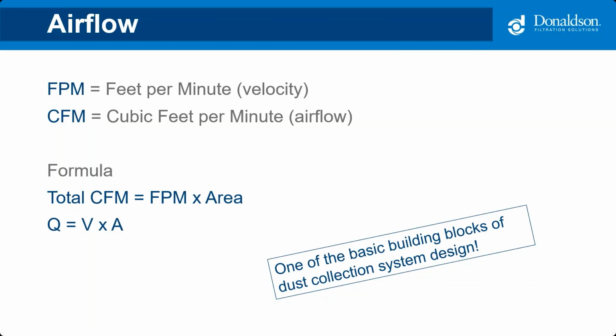We start at the pickup points and calculate using the formula to get the needed airflow for each pickup. The sum will then give us the total CFM needed for the system. This formula is also used when calculating the needed velocity within the ductwork. Throughout the design of the system, we refer to Q equals V times A over and over again.